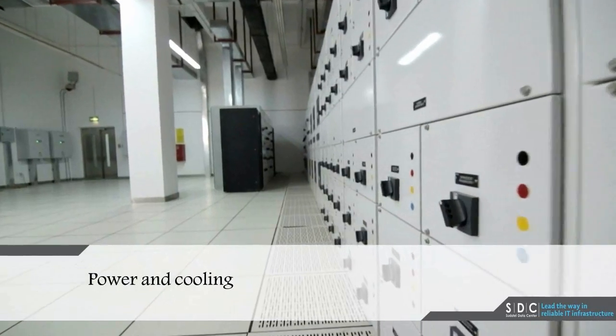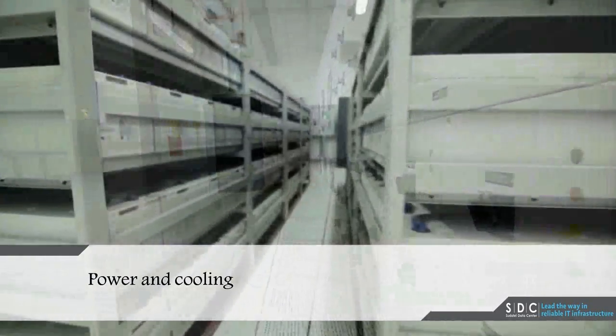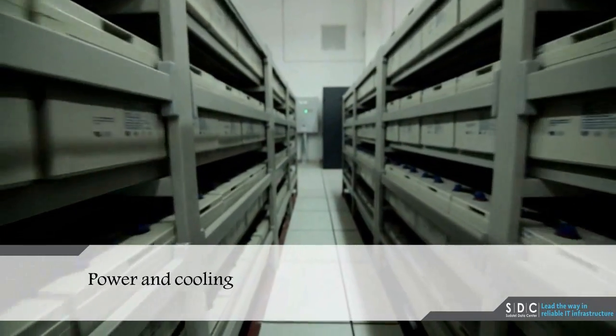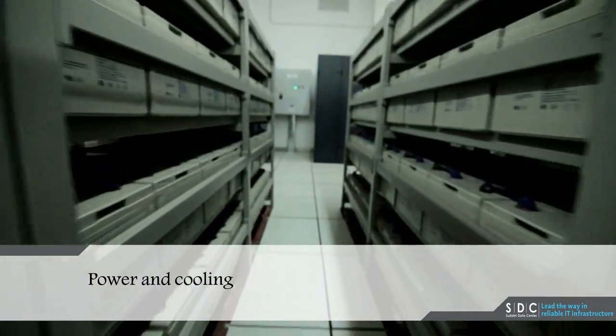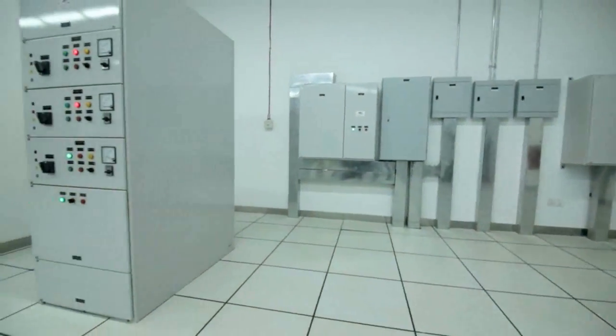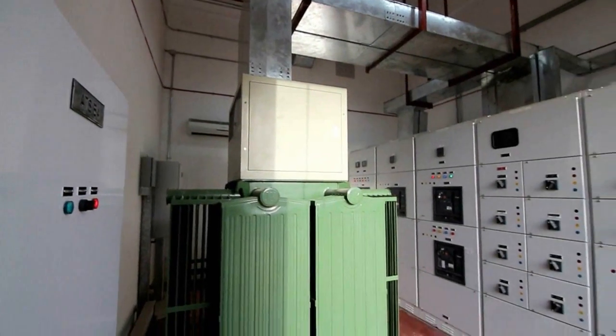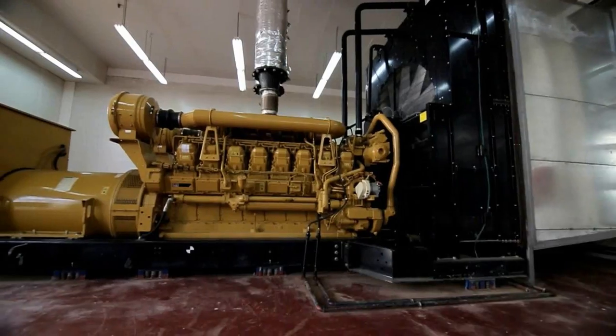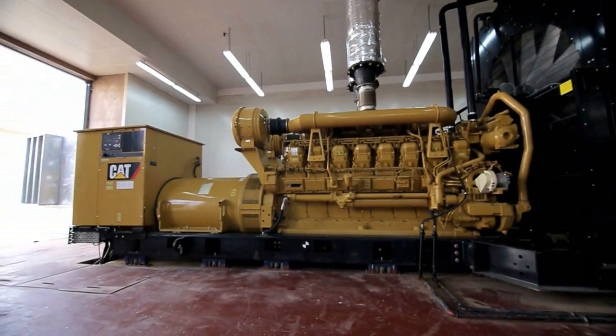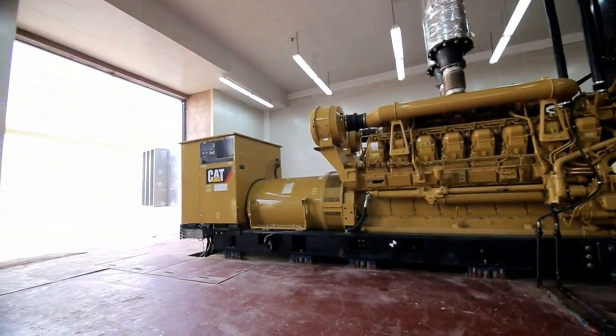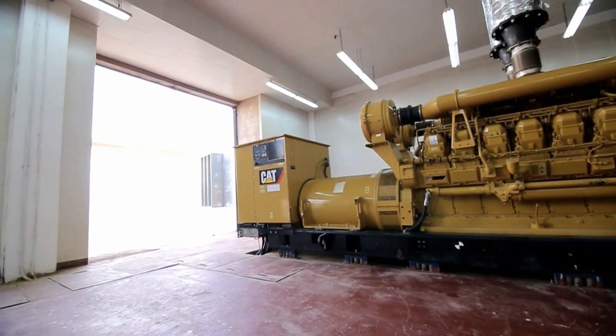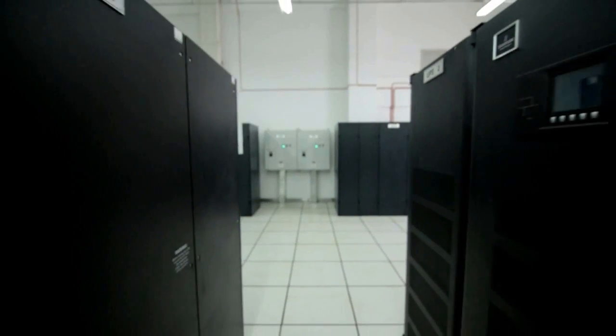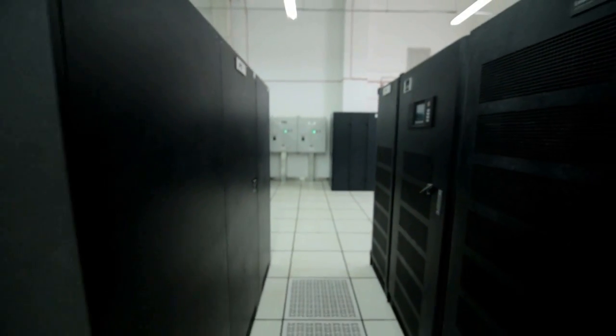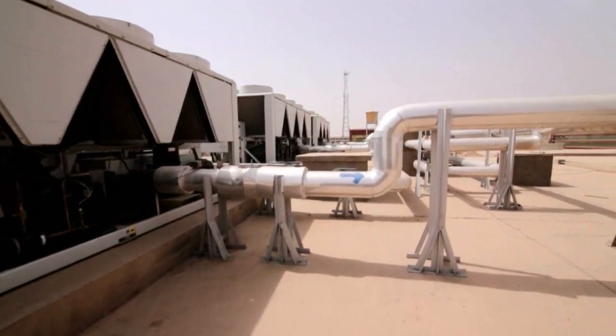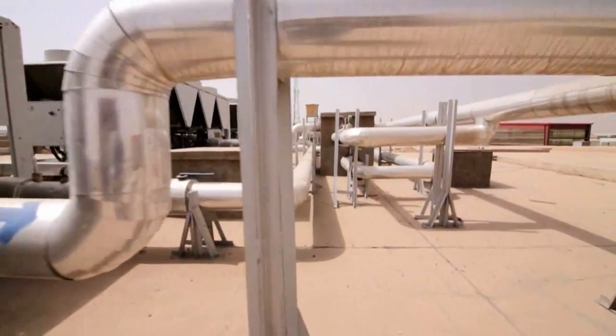Power and cooling. The center is supplied with various power and backup sources to ensure there are no power cuts, 2N+1. The center also has dual power supply lines with capacity 4MVA each from two separate stations and a fuel tank reservoir with enough fuel to keep the center running at full capacity via diesel generators for 7 days, in addition to UPS and batteries which feed the sources.